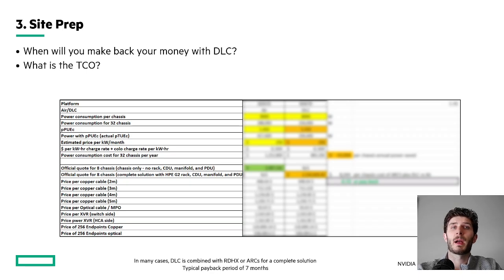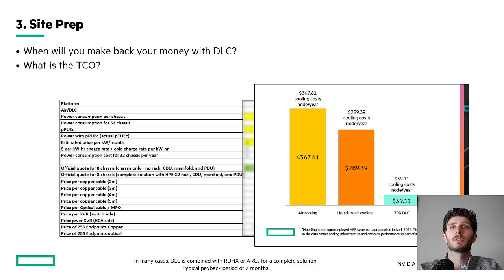The typical payback period we've seen is about 7 months, and the result is pretty staggering when we consider the costs associated with cooling: about $367 per year in this arbitrary example. Whereas if you're using liquid to air, it goes down to $289, and if you're using DLC, direct liquid cooling where you're getting air off the chip, it goes to $39.